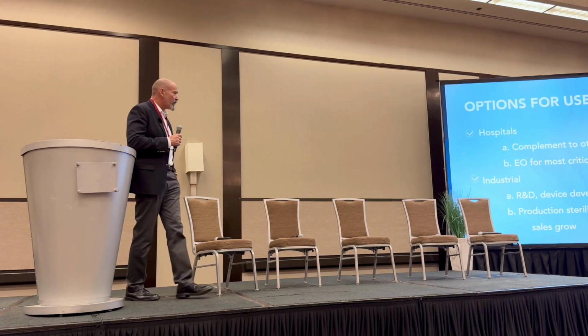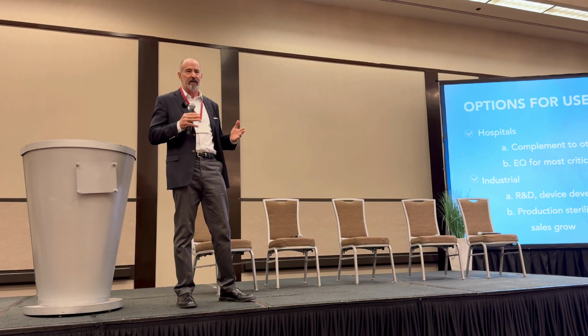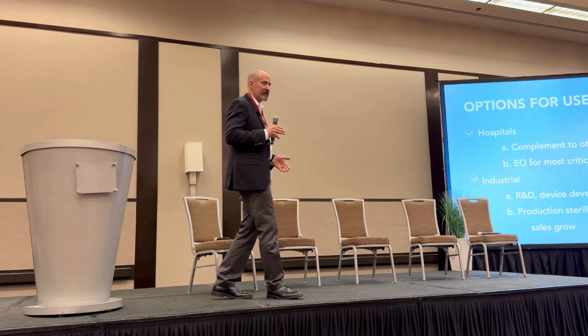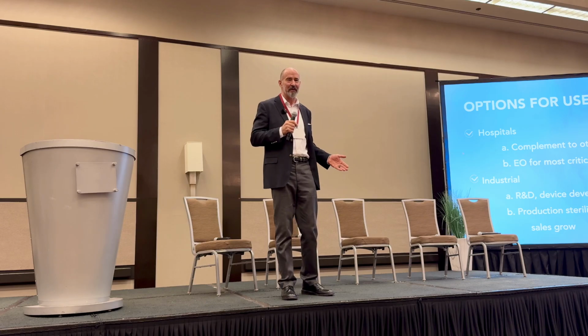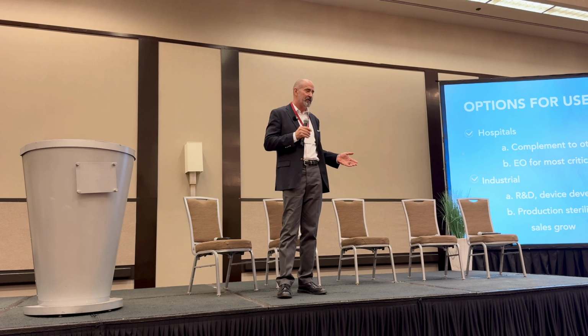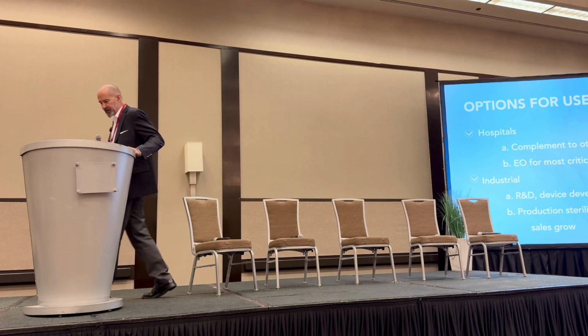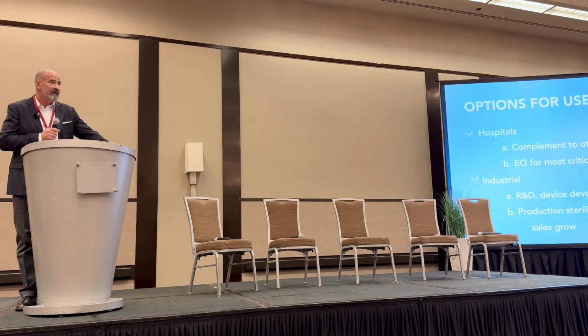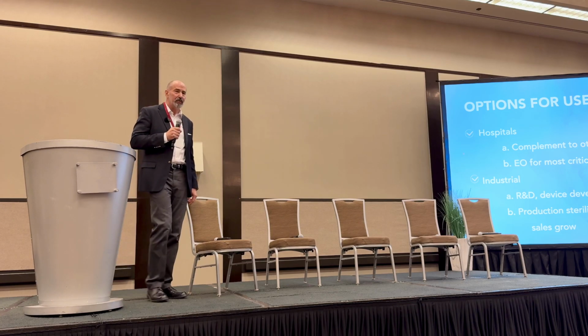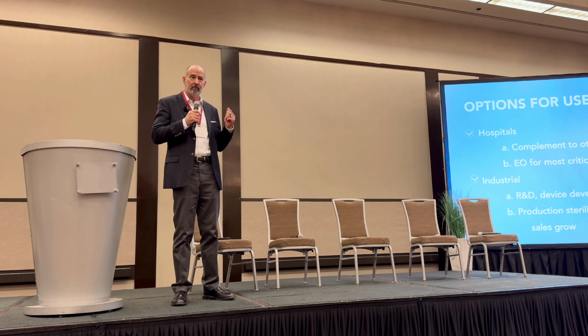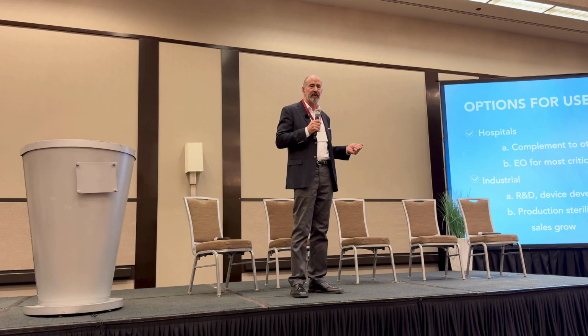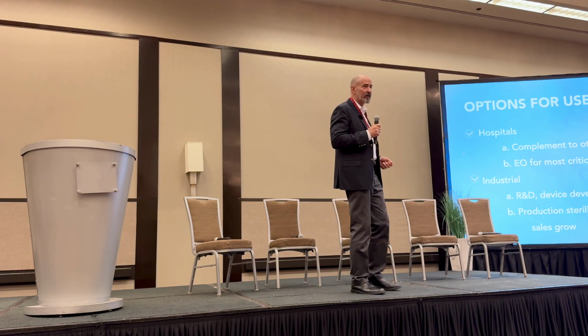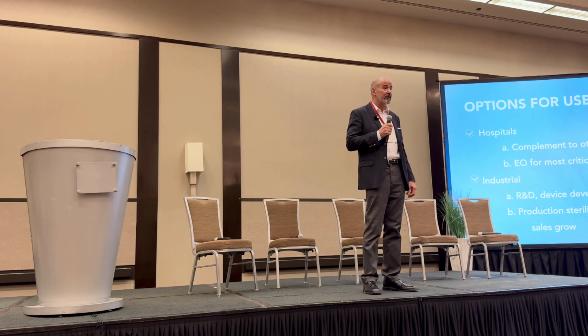Options for use. We've had a discussion already about the challenge of high-level disinfection versus sterilization. I serve on a number of AAMI committees, and I'm very glad to see other AAMI veterans here in the audience. There is a passionate debate going on in these AAMI committees about sterilization, or is high-level disinfection good enough? And right now, AAMI is recommending the sterilization of scopes. FDA is recommending the sterilization of certain scopes. There are a lot of elements in the industry that are resisting this. And I don't think that hospitals are going to move to the sterilization of all scopes anytime soon. But there are certain particularly critical scopes, like duodenoscopes. There are certain patient types, patients who are immunocompromised, where it would be very nice to have a sterilization resource.